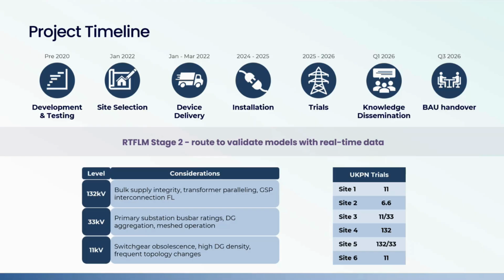So in practical terms, UKPN has installed and trialed 6 RTFLM devices across 6 substations. And given the nature of the innovation project, or the challenge, sorry, that we're trying to tackle, we saw the value in expanding the evidence base beyond a single DNO. And that was also a reasoning for us joining this consortium and investing in this project heavily. The sites were chosen to reflect very different challenges, from 11 kV network with aging switchgear and high distributed generation density, through 33 kV meshed primary substations, and up to 132 kV, where transformer paralleling and GSP fault level limits become critical.